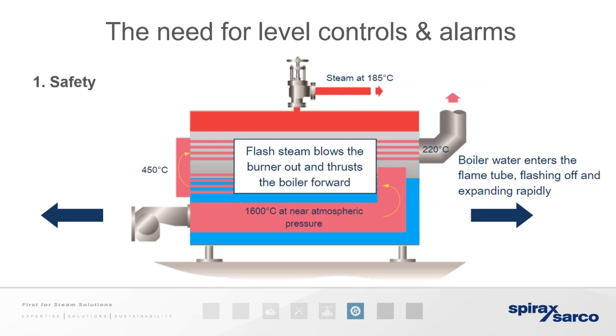So flash steam blows the burner out and then thrusts the boiler forward. The boiler water enters the flame tube, flashing off and expanding rapidly. This is what happens when a boiler collapses. If there's a hole into here, the burner would be put out by the sudden inrush. That high pressure water at high temperature would then expand in this tube, and it can cause a kind of explosion via implosion. So that's why we need to make sure that these boilers are well treated and well looked after. If this happened at 10 bar, for instance, the pressure released would be quite large.